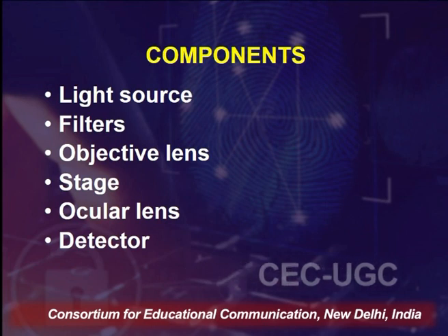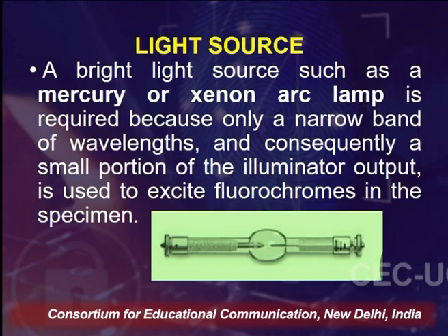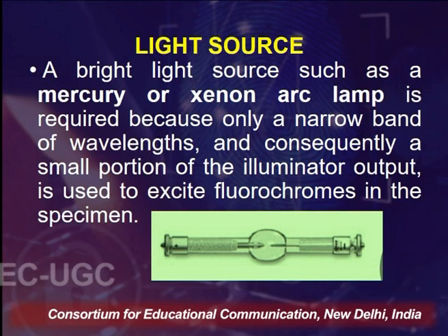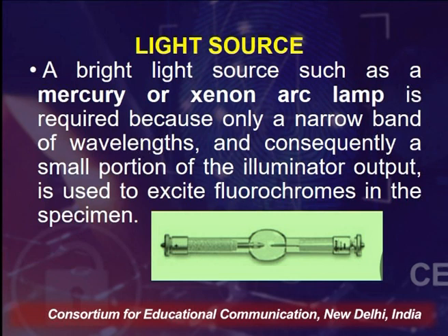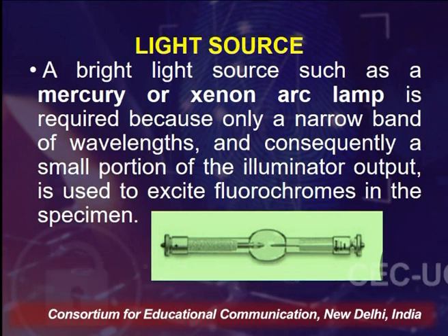The components of the fluorescence microscope include a light source, filters, objective lens, stage, ocular lens, and the detector. The light source could be a bright source such as a mercury or xenon arc lamp, which is required because only a narrow band of wavelengths — and consequently a small portion of the illuminator output — is used to excite the fluorochromes in the specimens.